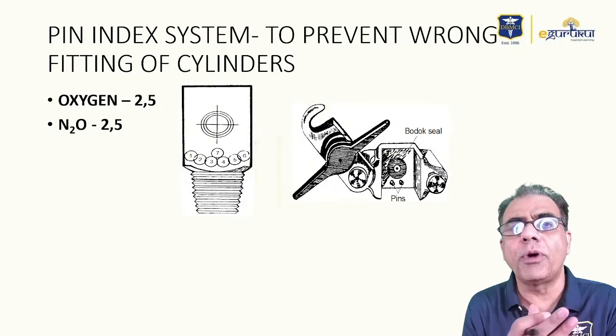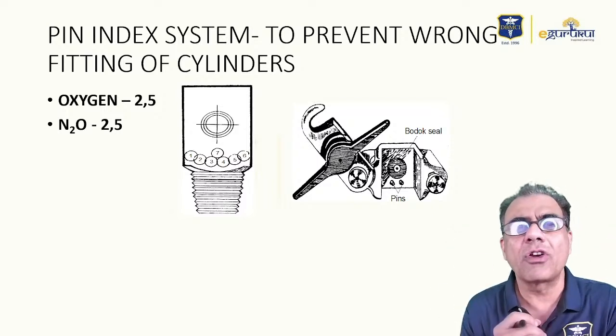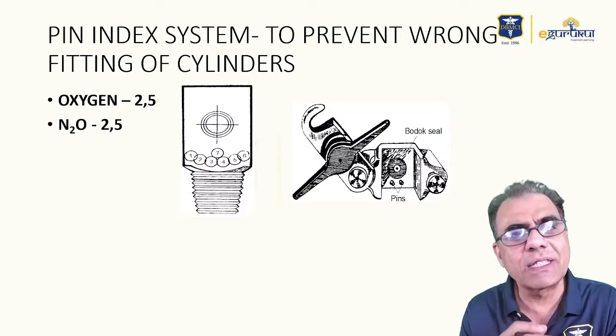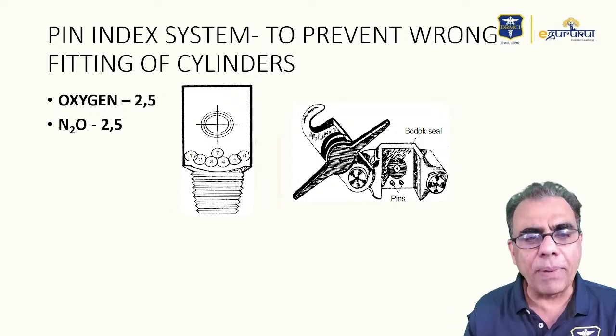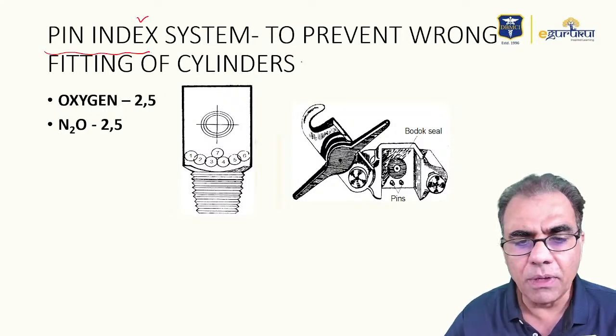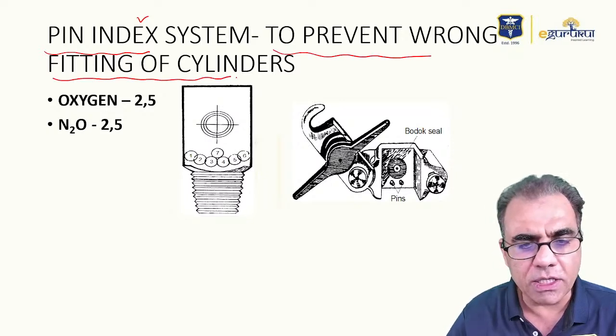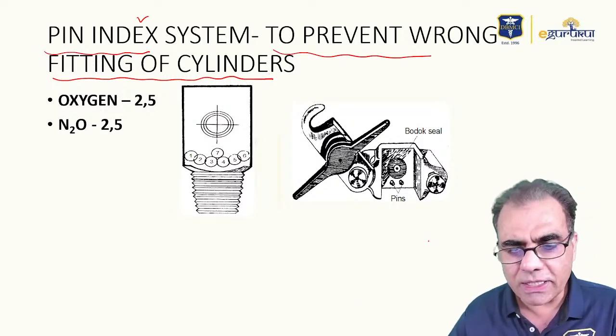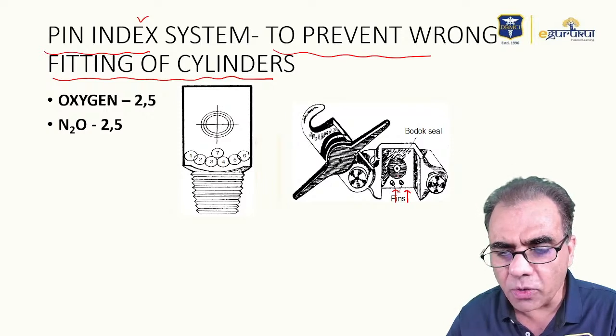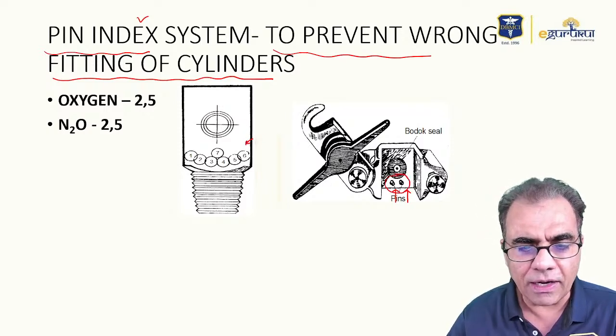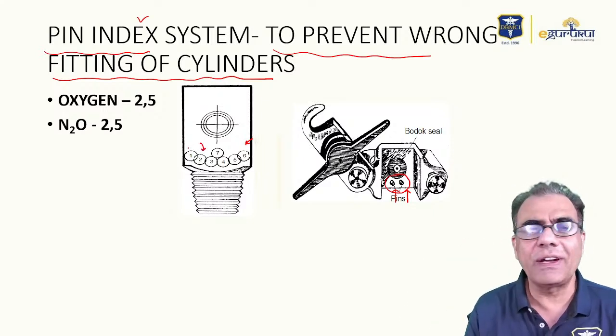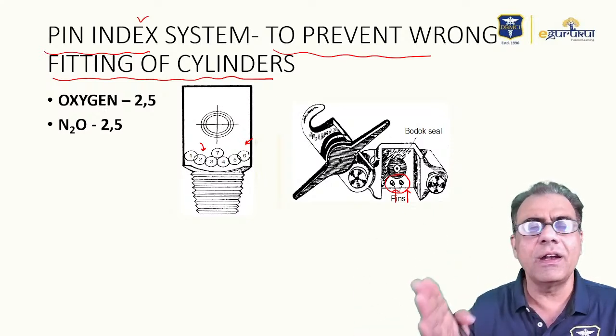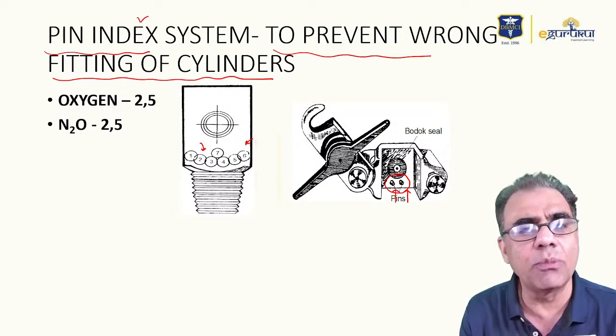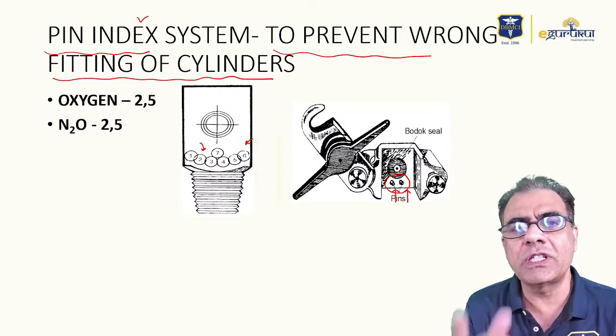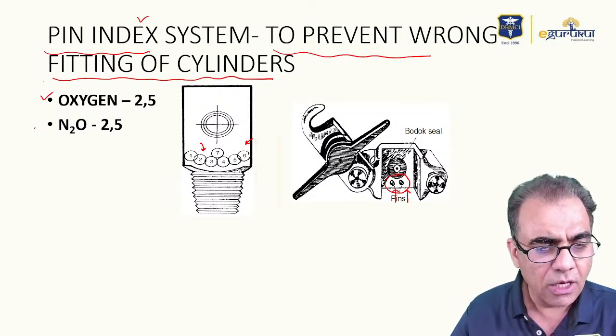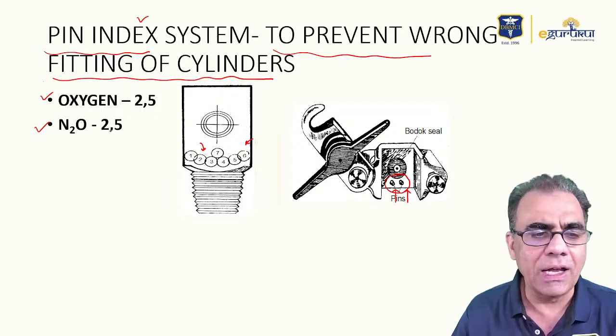Another very important thing is that we should prevent wrong delivery of the gases. Cylinders are attached to the anesthesia machine, and at that place a pin index system has been devised. The aim of the pin index system is to prevent wrong fitting of cylinders, so you don't fit a wrong cylinder at a different position. It consists of two pins, and corresponding to the pin positions there will be holes in the cylinder. The pin index position is defined for all gases. However, in modern-day practice only two cylinders are attached to the anesthesia machine, oxygen and nitrous oxide. So you have to know the pin index positions of oxygen and nitrous oxide only.